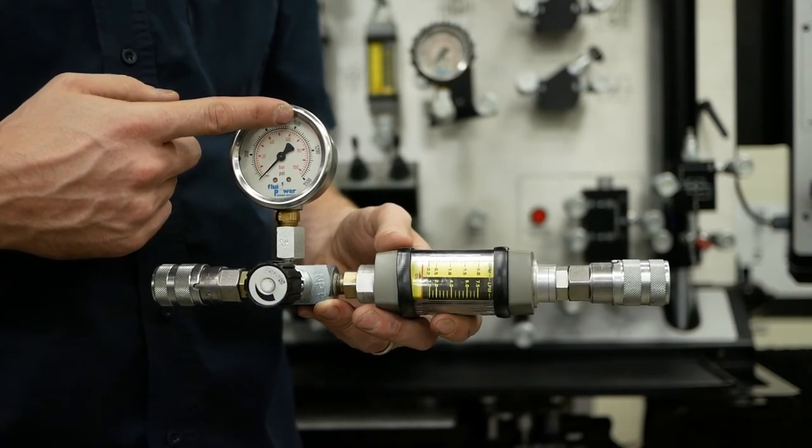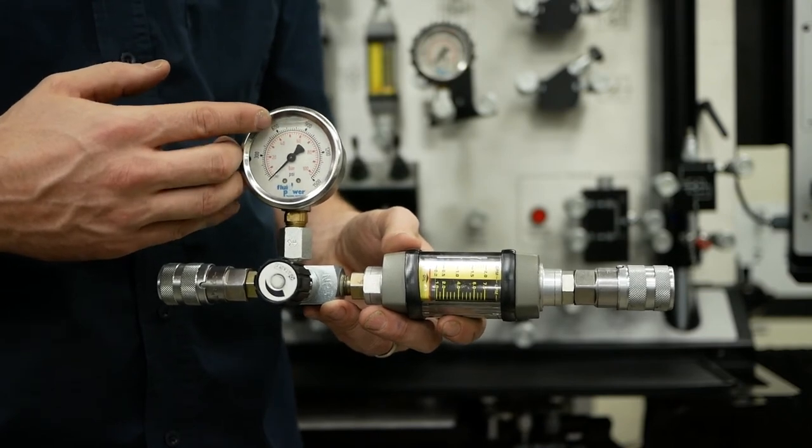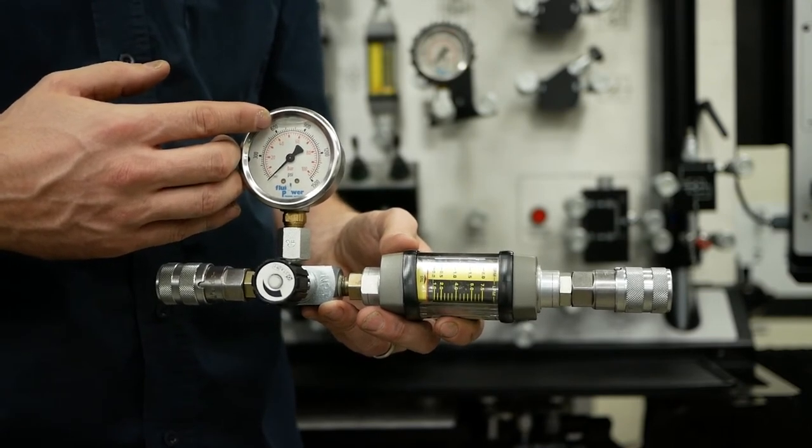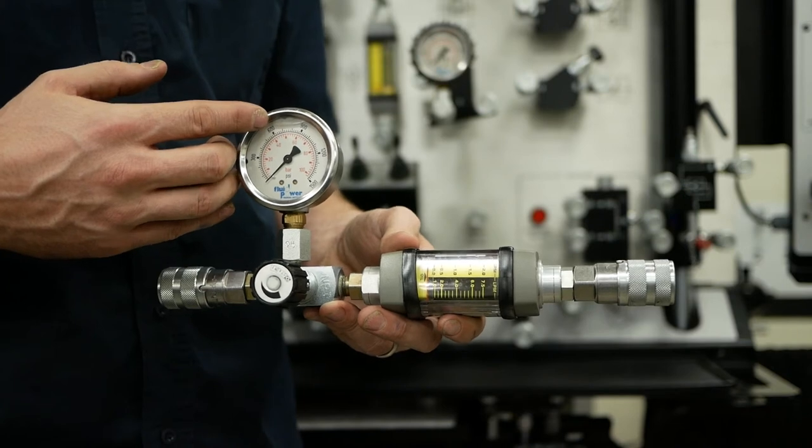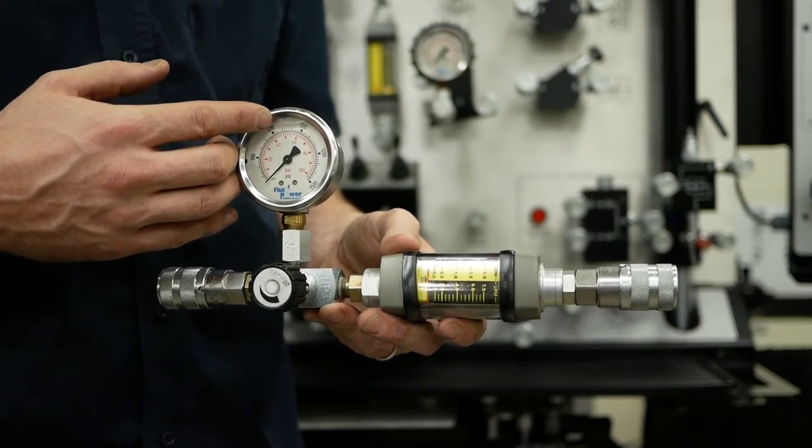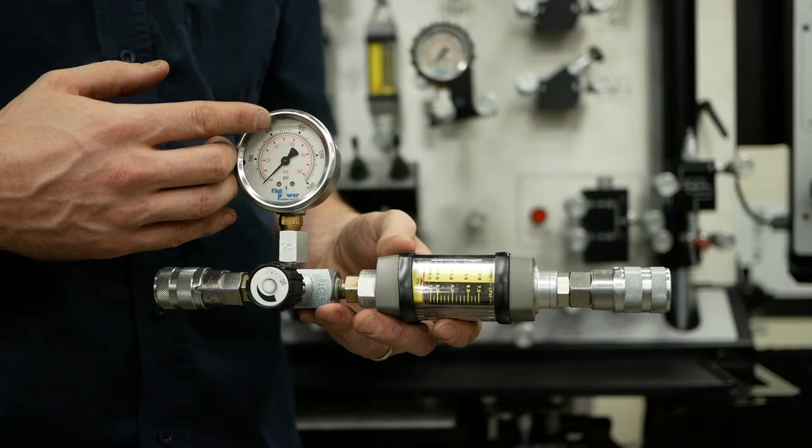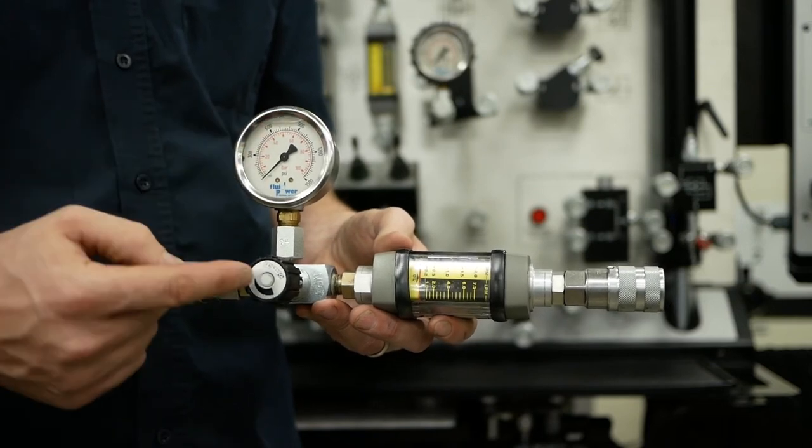As we measure its volumetric efficiency drop from low pressure to high pressure, of course that volumetric efficiency drop is happening because the internal leakage is getting greater with a greater pressure drop as we create the restriction on the outlet side of the pump port.